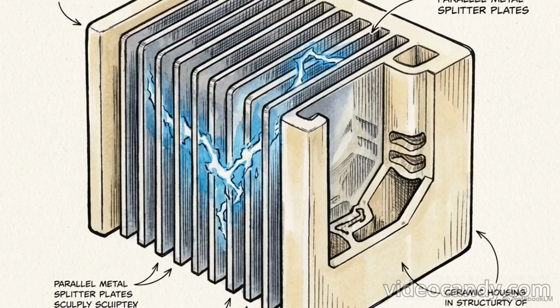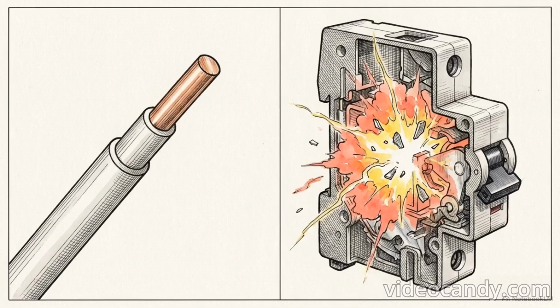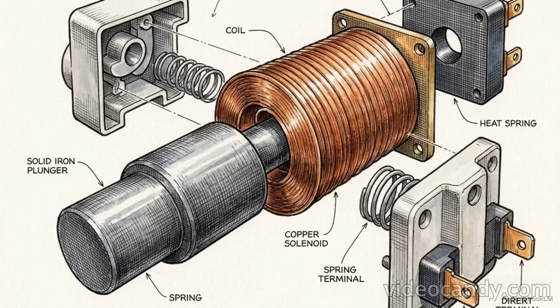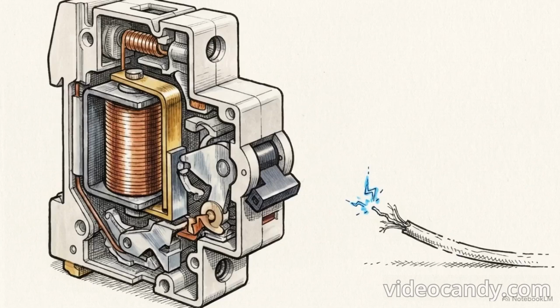A specialized internal arc chute matrix catches the resulting electrical arc and stretches it until it extinguishes safely within the plastic housing. The MCB is a brilliant piece of dual-stage hardware. It protects wires from melting and isolates short circuits before they explode. But its physical latches require massive volumes of current or heat to trigger. Because of this high activation threshold, the MCB is completely blind to low current anomalies.